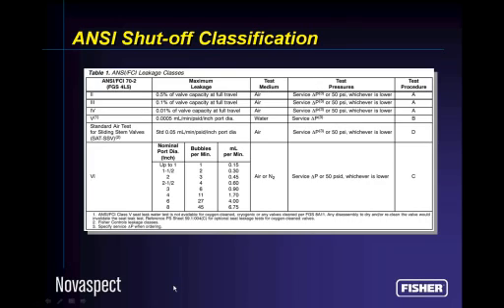Another important characteristic that you need to identify for us is the ANSI shutoff classification. We like to think of your control valves as just that, control valves. And indeed, the control valve's basic design criterion is to be a good flow controlling element and to do that with the minimum amount of variability. But sometimes you want to save some money and you want to assign a particular shutoff classification to the control valve simultaneously. So there is an ANSI specification that you can reference, and we certainly know all about it.